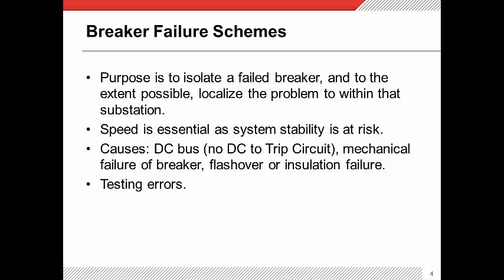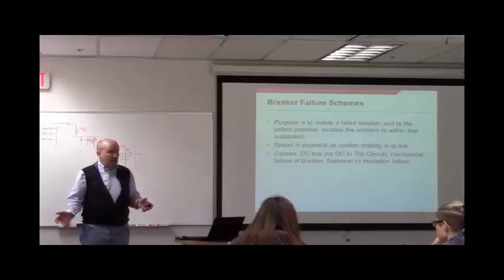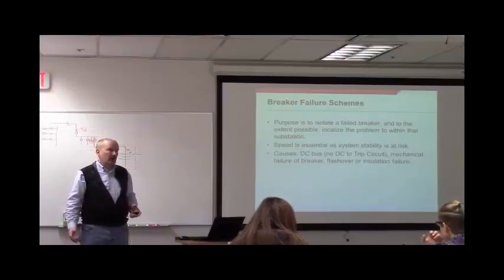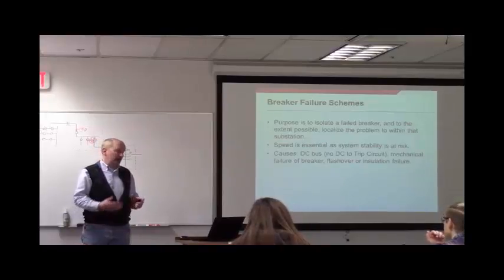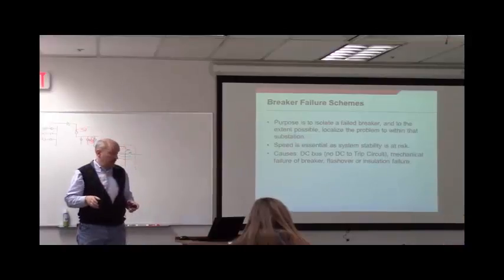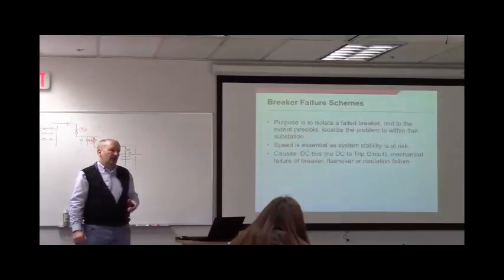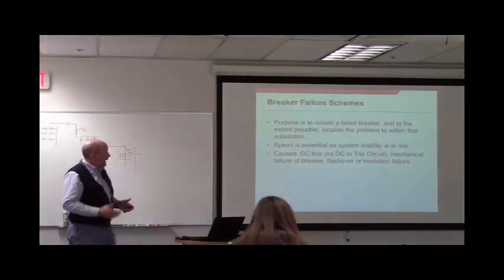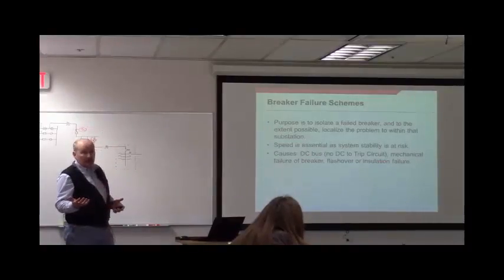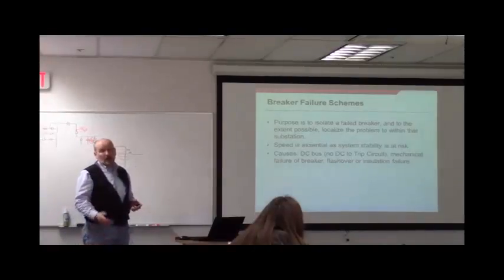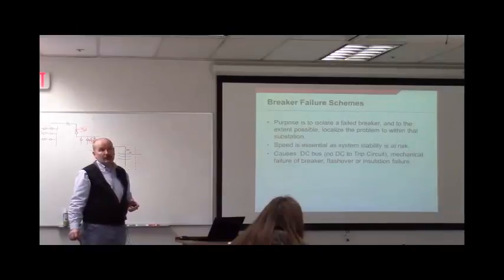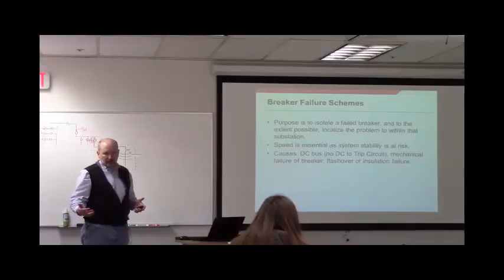A typical — probably the most common — cause of breaker failure is a problem with your DC supply, which is your control voltage for the circuit breaker. No DC supply, no trip. Human error is also very common: leaving a test switch open. Those little test switches — a human forgets to close one and you've now got an open circuit. You could also have mechanical failure, insulation breakdown within the circuit breaker, or a flashed-over breaker. Low gas with a block-operate policy is another cause.